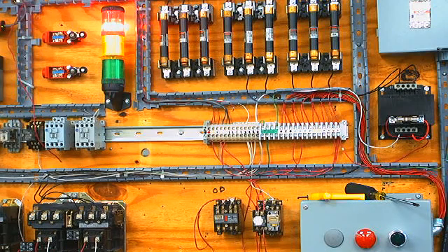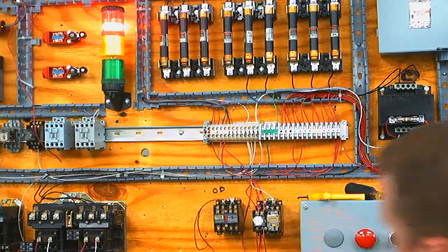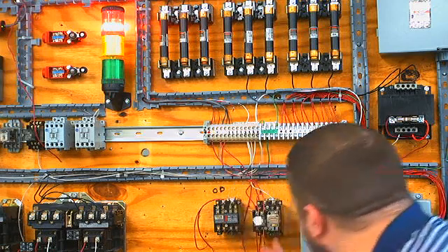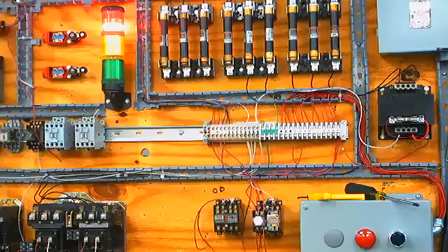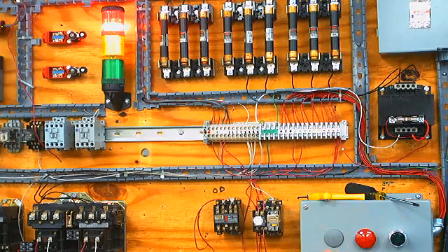See that? And I can make adjustments on this timer by this little dial here. You increase the time by doing that. So for off delay, when you push a button, it instantly changes state, so there's no timer variation. Think about the delay in the timing happening when the coil gets turned off. That's why it's called off delay. And on delay is the opposite. So when you push the button, nothing might happen, right? Correct. Okay. And I will do an on delay in a minute.